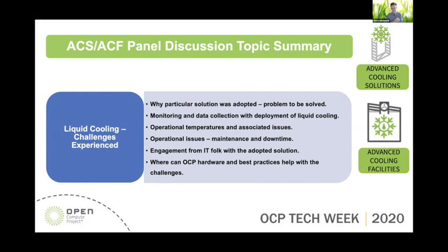So if everything else failed, if all other safeguards didn't work out, we had leak detection at every level within the racks, and that would act like a ground fault interrupt in your bathroom and shut the power to those racks off at the panel. Because the last thing you want to do is be searching for the source of a leak in an energized rack. So those are two approaches we took to minimize risk. Make sure your power goes all the way back and is turned off at the panel. And we consider it a best practice to circulate liquids under negative pressure.